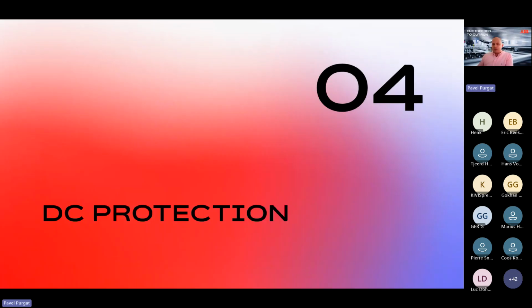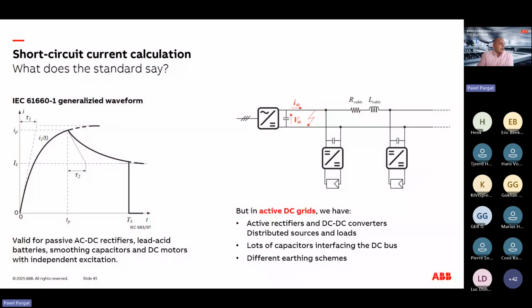Now, one of the things that people are always afraid about is the protection of DC systems. This is not surprising. I mean, there is not so much experience, and as well, there are not that many devices, at least that's usually claimed. When we look at the standards, there is one relevant standard at the moment that makes sense to look at, and that's the IEC 61660, which tells us how to calculate a short circuit current in a DC grid. Now, this standard was, however, designed for DC systems that usually consist of passive rectifiers, lead-acid batteries, and large smoothing capacitors, and not so many loads, and for sure not many active converters connected together.